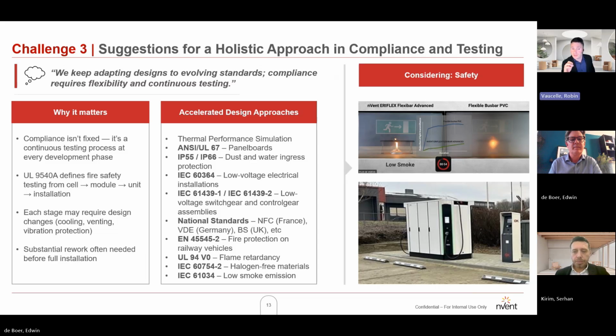By simulating worst-case scenarios, designers can evaluate propagation risk and implement strategies such as insulation, venting, or cooling to prevent cascading failures. To stay ahead, we need accelerated design approaches, thermal simulations, IP-rated protection against water and dust, and adherence to global standards such as IEC 60364 for low voltage installation or IEC 61439 for switchgear assemblies.